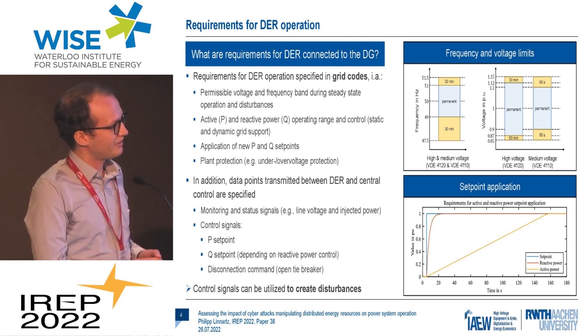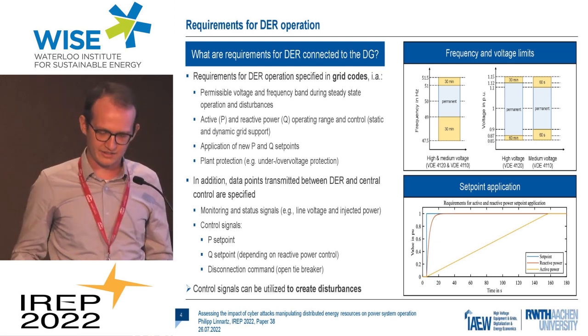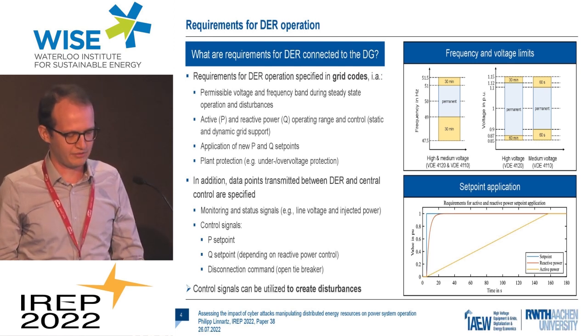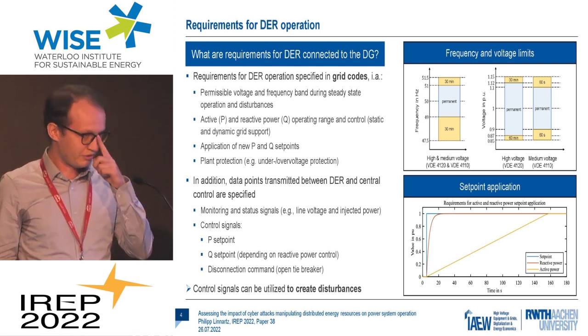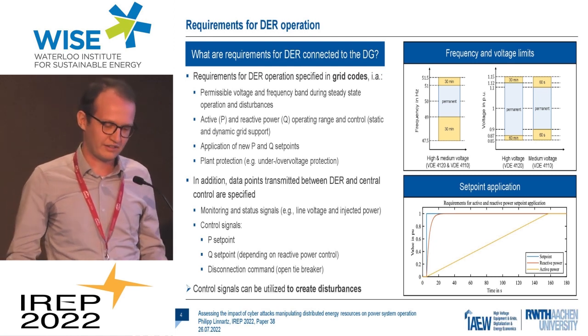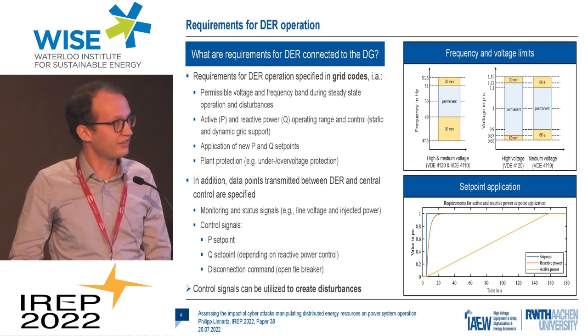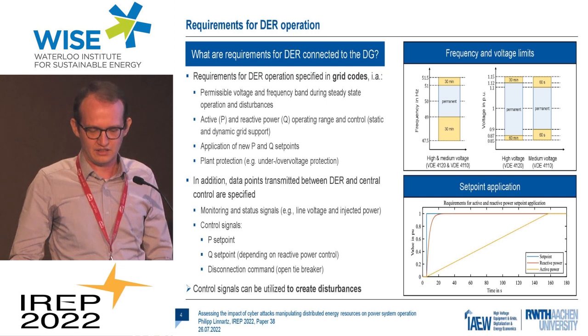For reactive power, it's a bit faster, within about 20 seconds, with this kind of exponential behavior. Also, plant protection requirements are specified, so that if, for example, the voltage is outside the specifications of the voltage band, the DER should disconnect after some specified time.